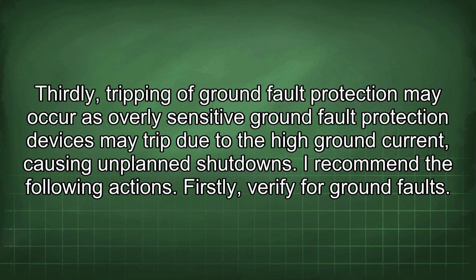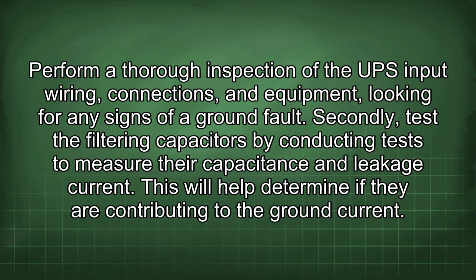I recommend the following actions. Firstly, verify for ground faults. Perform a thorough inspection of the UPS input wiring, connections, and equipment, looking for any signs of a ground fault. Secondly, test the filtering capacitors by conducting tests to measure their capacitance and leakage current. This will help determine if they are contributing to the ground current.